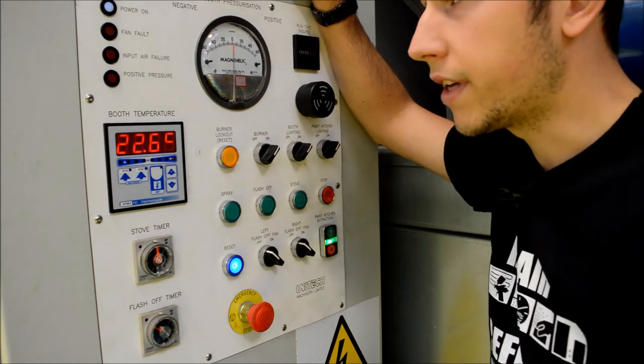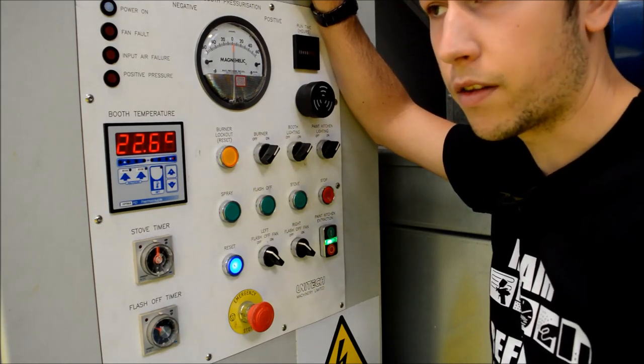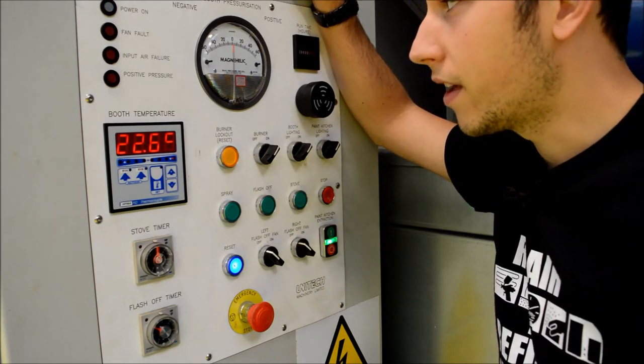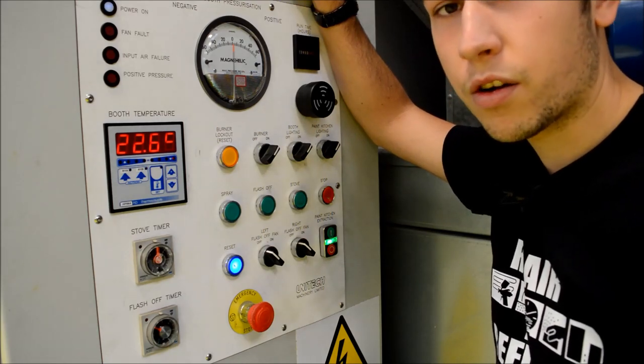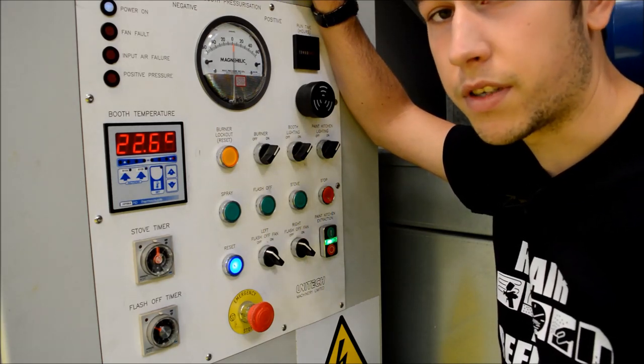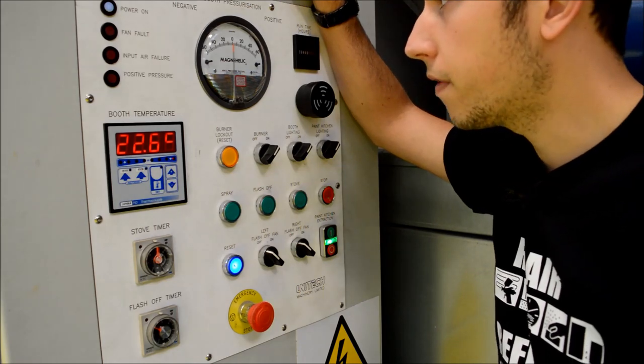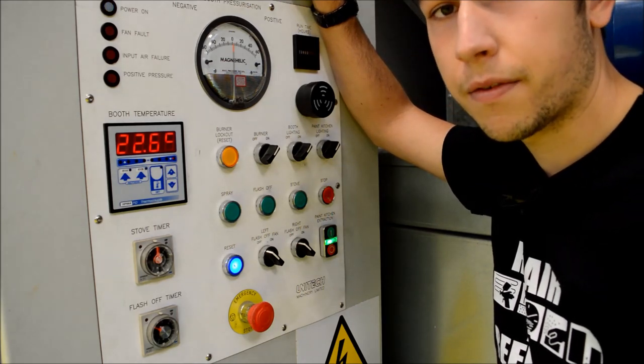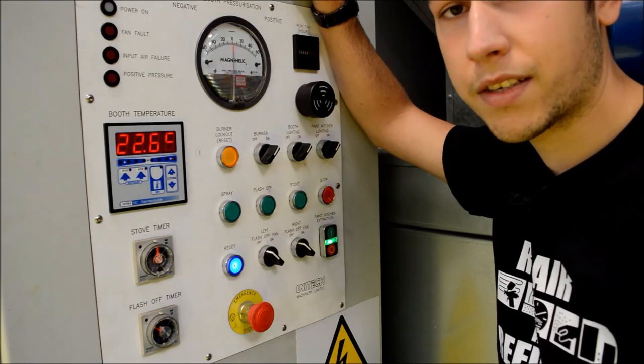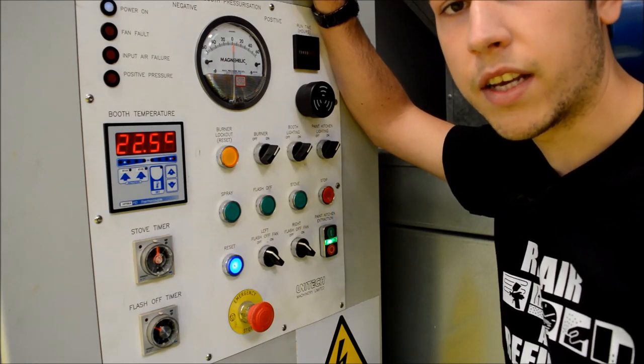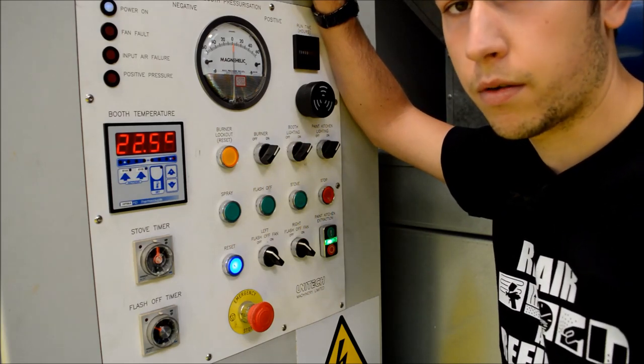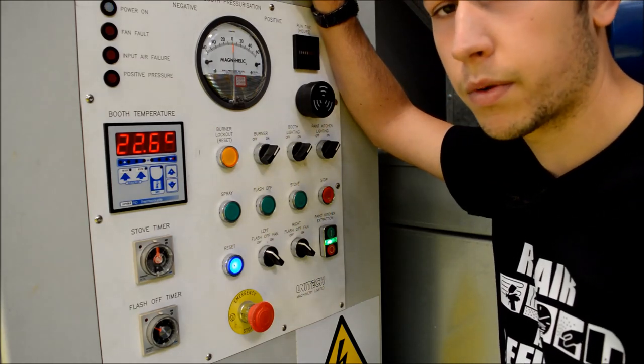If the booth pressure is positive and the doors are blowing open, if you're trying to find out what the fault of that is, that could mean that the spray booth filters need changing. If the spray booth pressure is negative, that means the booth is basically sucking more air than it is blowing into that booth, so that might be a good time for you to change your roof filters as well.